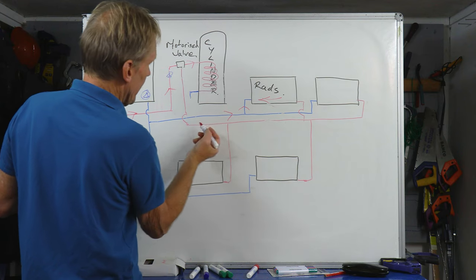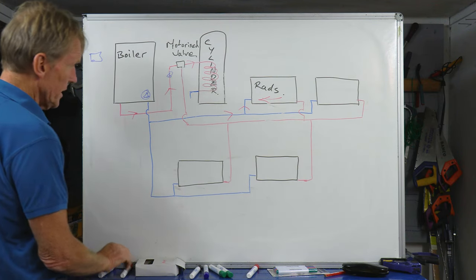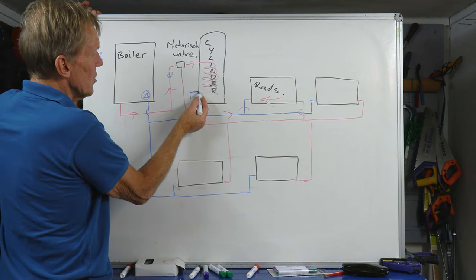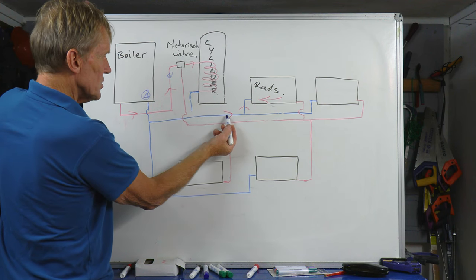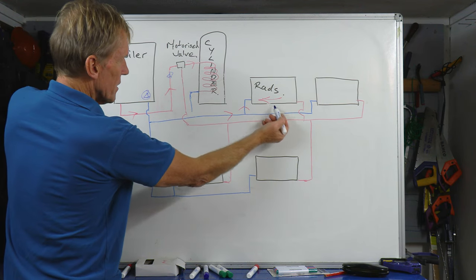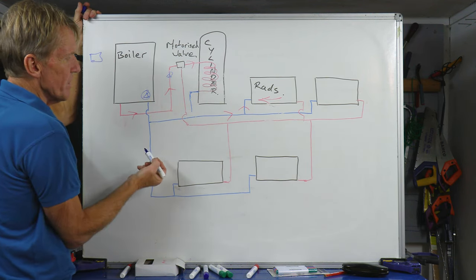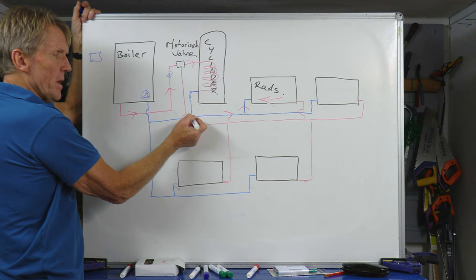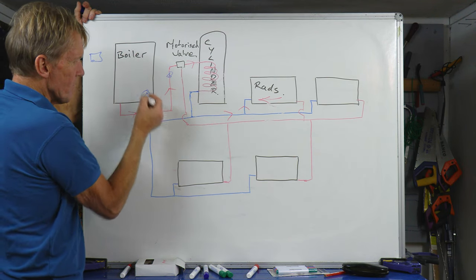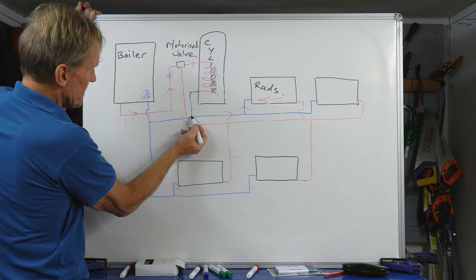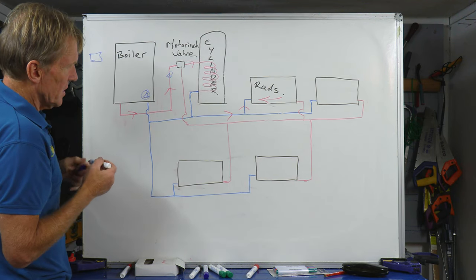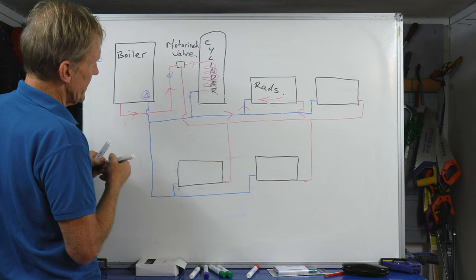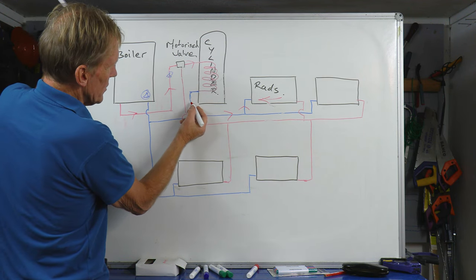Now the reason that's happening is because a lazy plumber or an ignorant plumber or whatever, or a DIYer, has taken that return from the cylinder and they thought, oh look, this is the return from the radiators, it's going back to the boiler anyway, I might as well hitch a ride on it. So they do their tee in that piece of pipe work there rather than in what we call the primary flow and return. So if they do that, what then happens is that that water can now circulate through the radiators the wrong way.